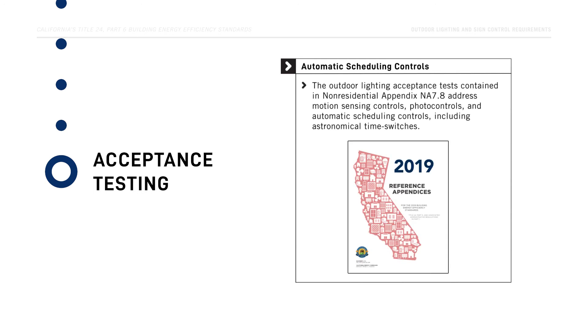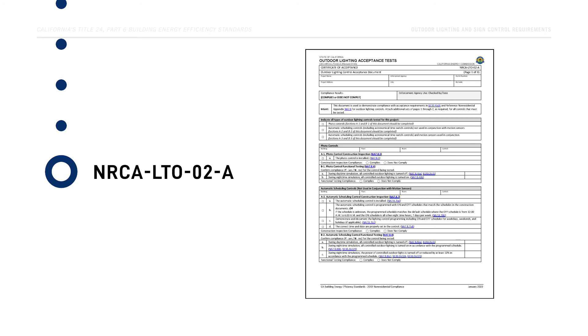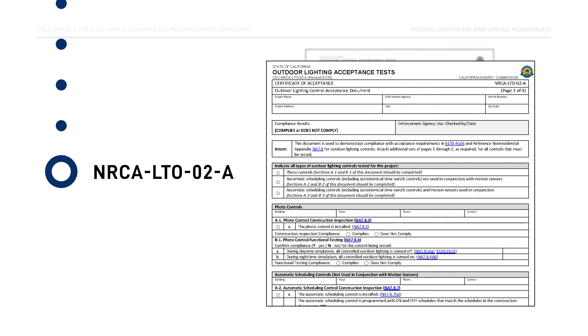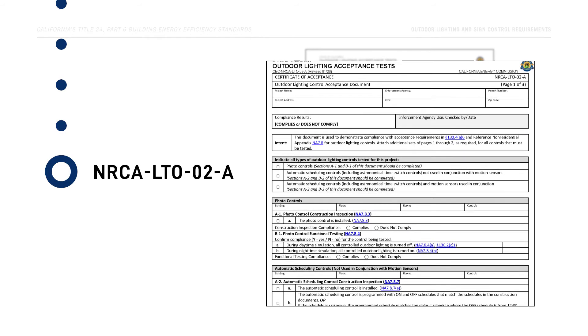The outdoor lighting acceptance tests contained in non-residential appendix NA 7.8 address motion sensing controls, photo controls, and automatic scheduling controls, including astronomical time switches. Acceptance test results for outdoor lighting controls are documented by the Certified Lighting Controls Acceptance Test Technician on the Certificate of Acceptance NRCA-LTO-02-A.